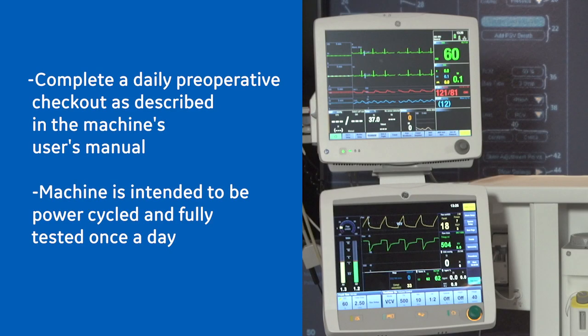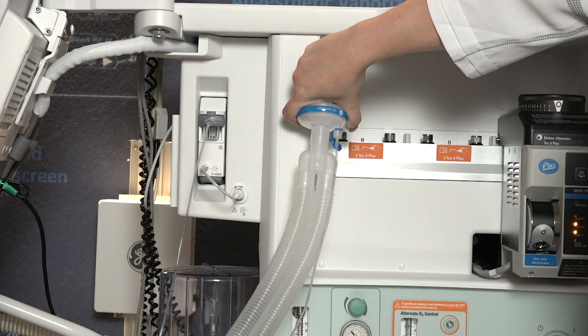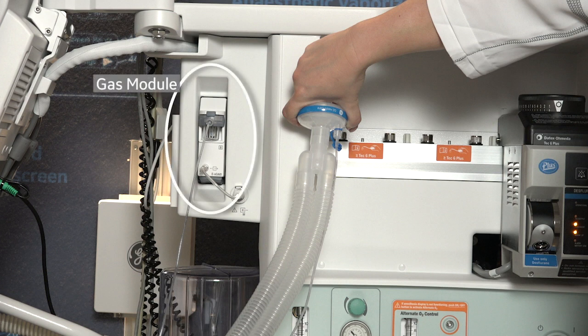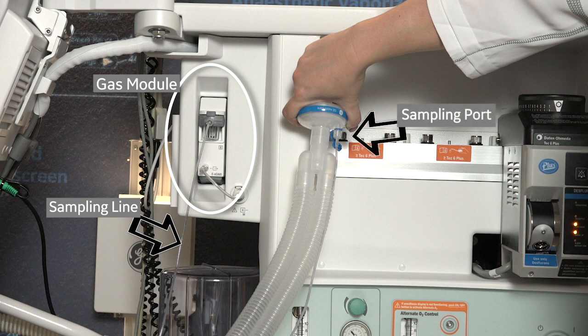Complete a daily peri-op checkout as described in the user's manual. The anesthesia machine is intended to be power cycled and fully tested once a day. All accessories that will be used during the case should be attached to the circuit to ensure accurate circuit compliance. When using a GE Healthcare respiratory gas module, make sure to connect the sampling line to the sampling port proximal to the anesthesia device with respect to the heat moisture exchange filter, or HMEF.